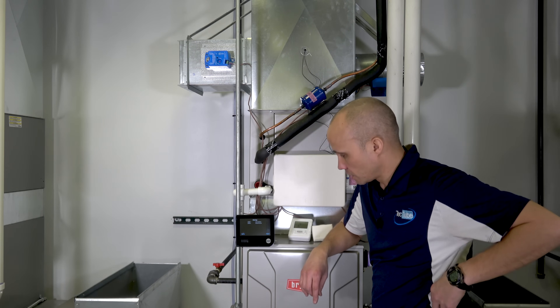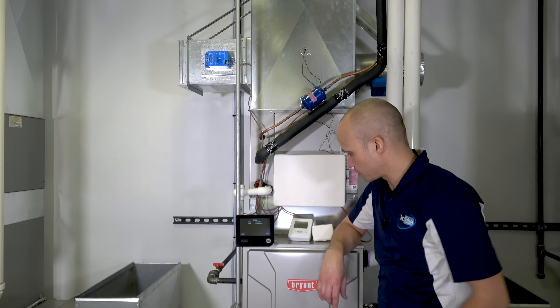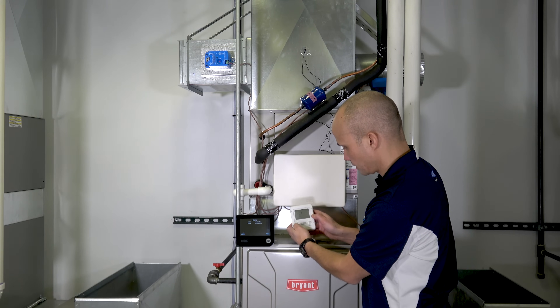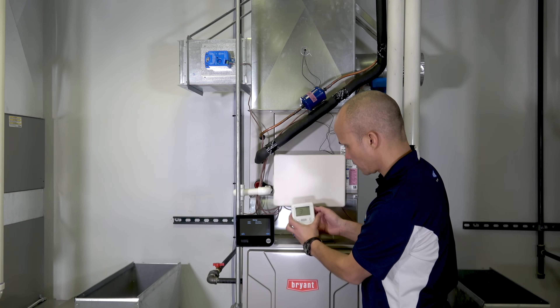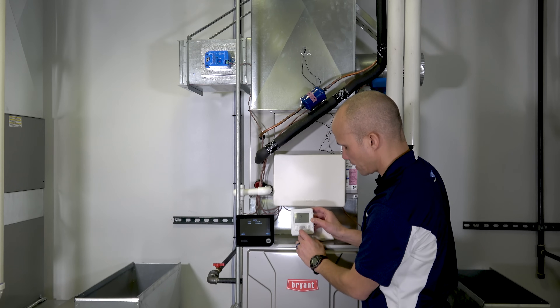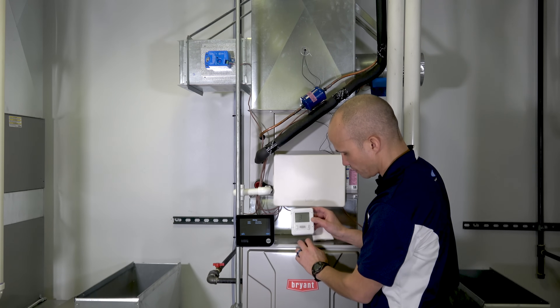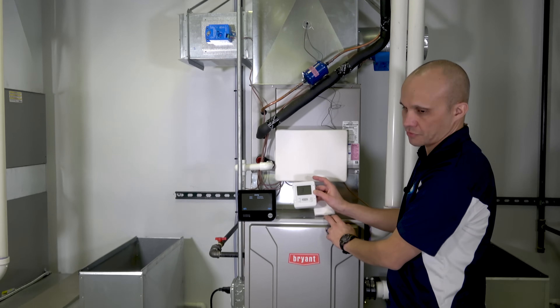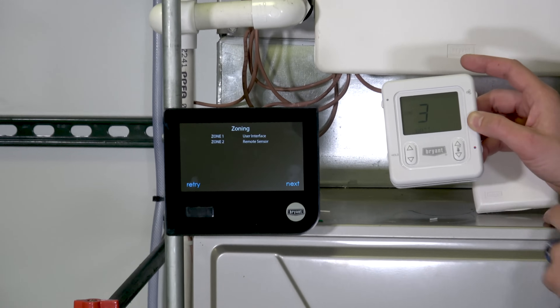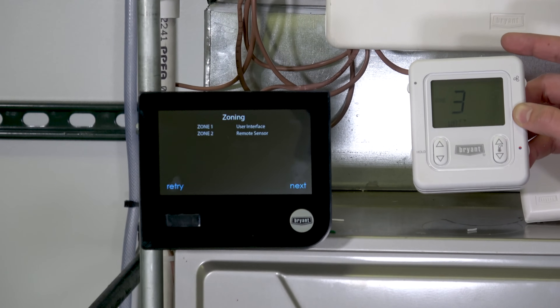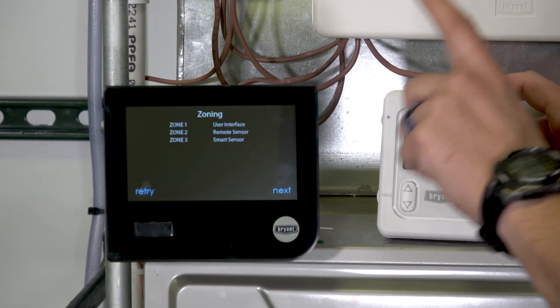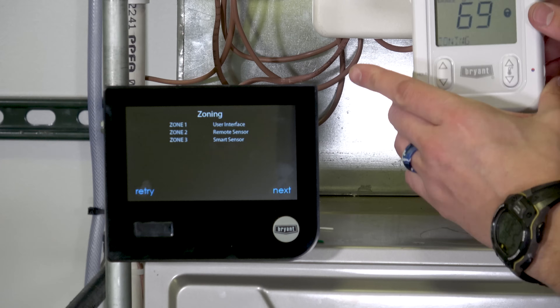It found two zones initially — zone one and zone two — but didn't find the smart sensor because I hadn't yet configured the zone number on it. I told it it's zone three and saved it. These smart sensors default to zone two, but for zones three through eight you need to give them an address. After telling it to retry, it found all three: user interface zone one, remote sensor zone two, and smart sensor zone three.